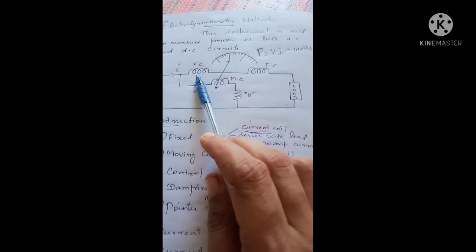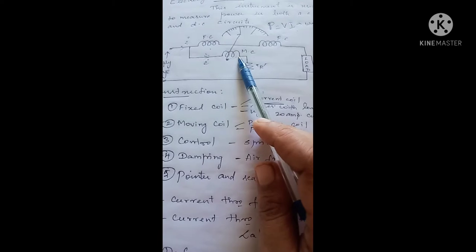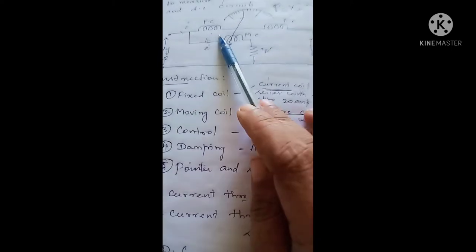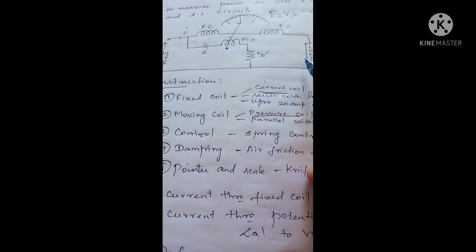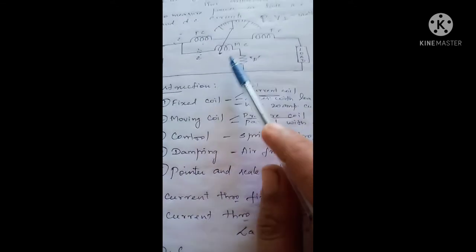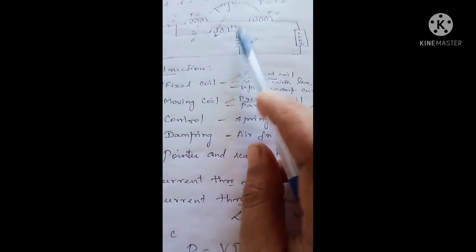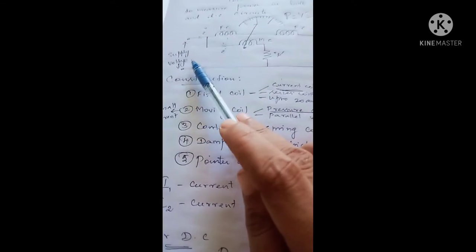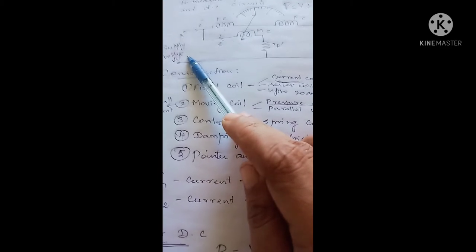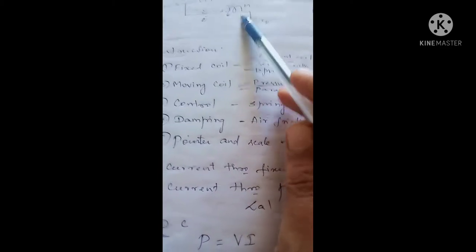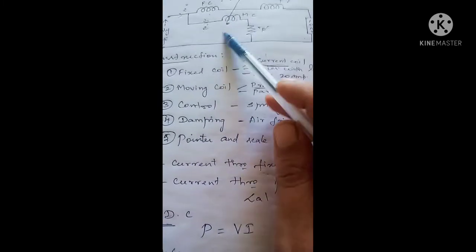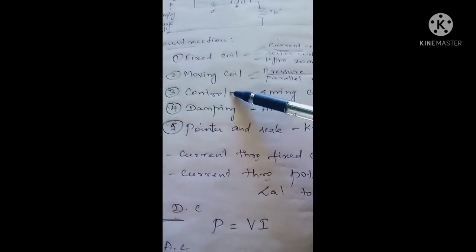The fixed coil is connected in series with the load and it carries the current to the load, so it's called the current coil. The moving coil is connected in parallel with the supply voltage and hence it's called the pressure coil or potential coil.